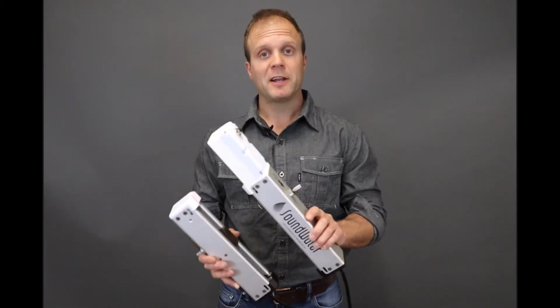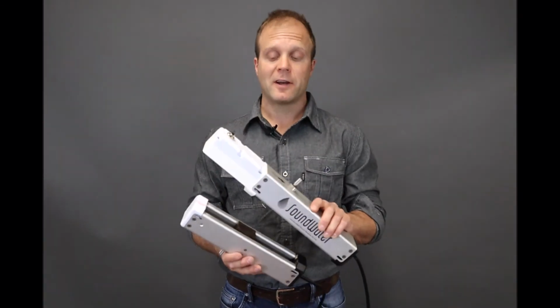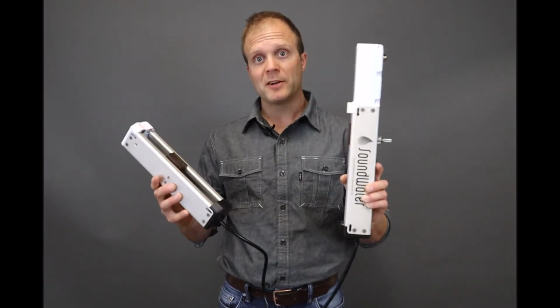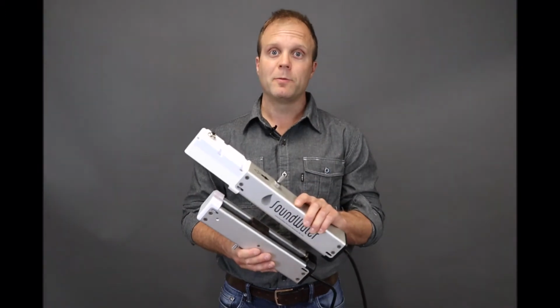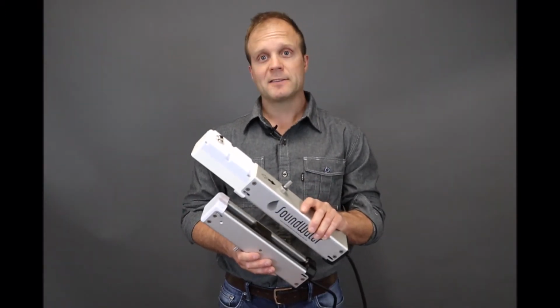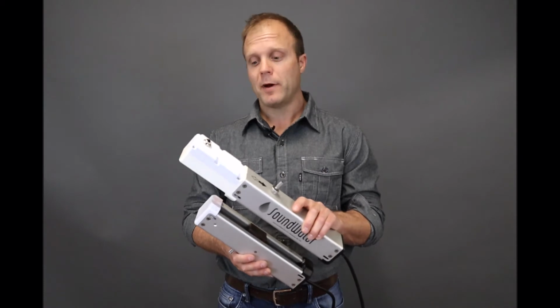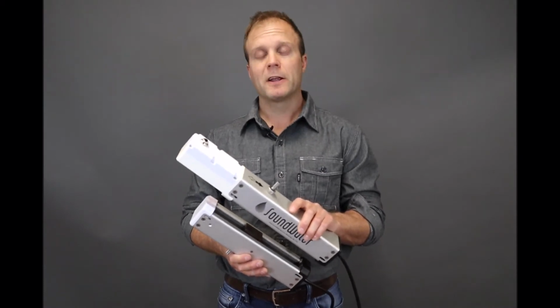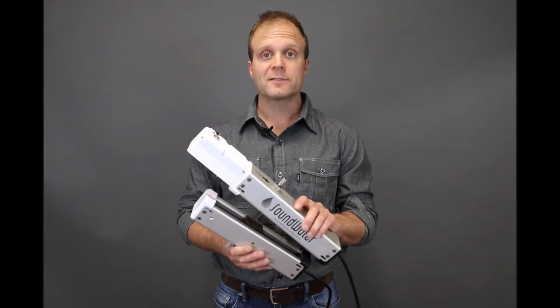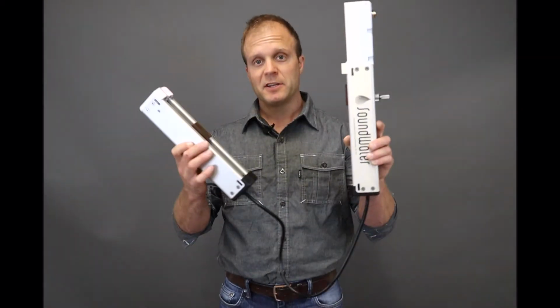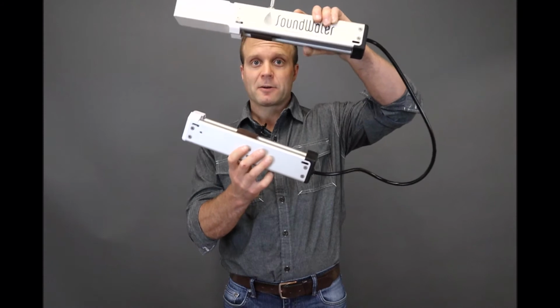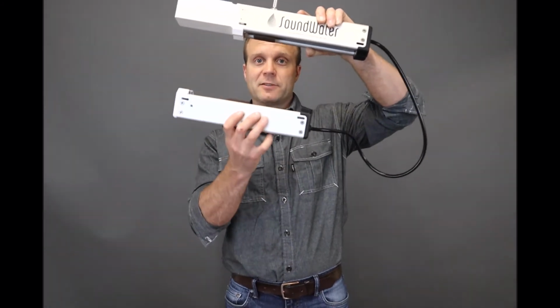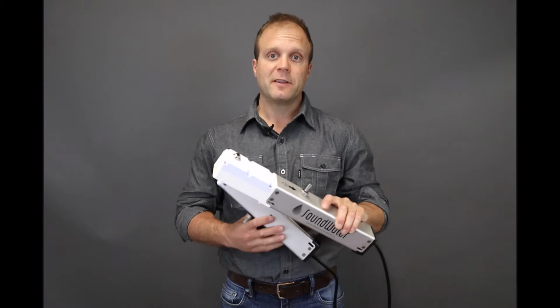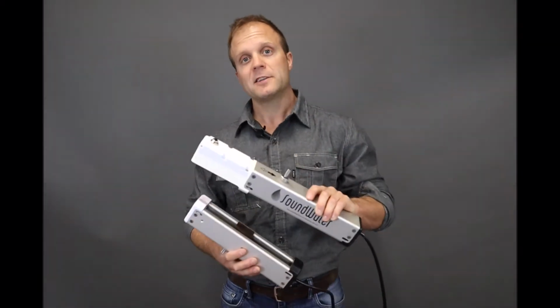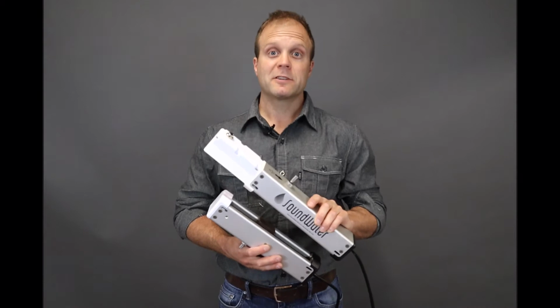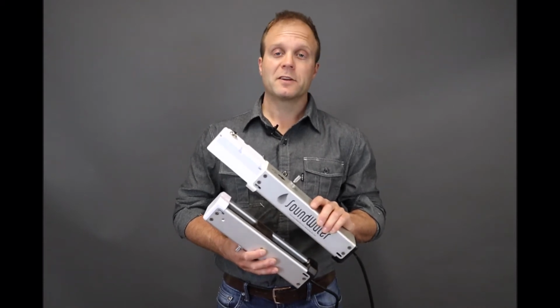For this particular application, we're going to install it on a fracking service line, and in addition to being able to measure flow, we can also use it to mark the presence of sand, acid, or other materials that are within the pipe. And we do this by looking at the ultrasonic energy loss within the fluid. So essentially the sound will come out of the top transducer, pass through the pipe, and enter the bottom transducer. And we look at the amount of energy that we transmitted versus what came out the other side. And in doing that, we can see how much energy is lost and infer that there's different material inside the pipe and fluid.